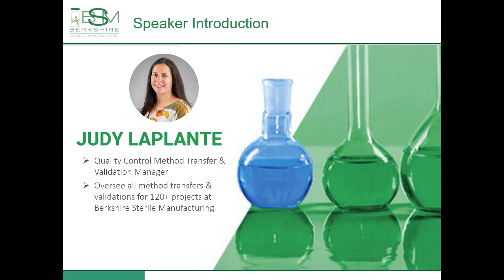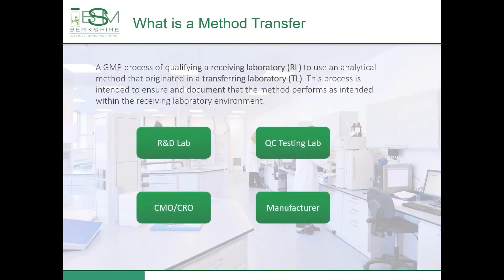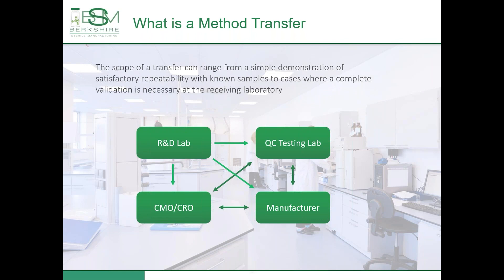Thank you, Sarah, for the introduction. Let's get right into it. What is a method transfer? A method transfer is a GMP process of qualifying a receiving laboratory to use an analytical method that originated in a transferring laboratory. The process is intended to ensure and document that the method performs as intended within the receiving laboratory environment. Method transfers can occur between multiple internal and/or external labs, and may or may not involve the original lab that developed and validated the method. An example is a procedure developed and validated in an R&D lab, transferred internally to the same company's manufacturing site, and again later transferred to an external contract organization. This process can take months or even years. The scope of a transfer can range from a simple demonstration of satisfactory repeatability with known samples to cases where a complete validation is necessary at the receiving laboratory.